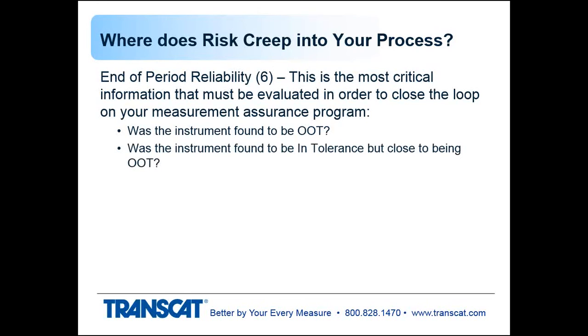Was it found to be in tolerance, but again, close to being out of tolerance? There are reasons where in-tolerance situations could cause risk in the measurements for the product. What impact does the lab's uncertainty have on this condition? And that's what I'm getting at. You could have an in-tolerance condition. The uncertainty of the laboratory's measurement then could have given a false accept reading in that region, and they should have called it out of tolerance.